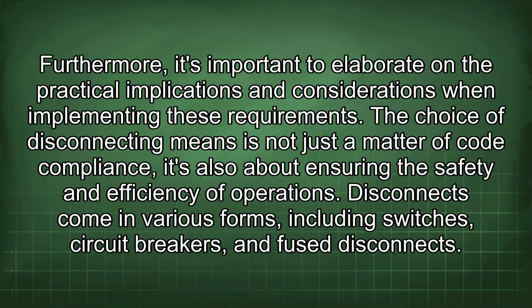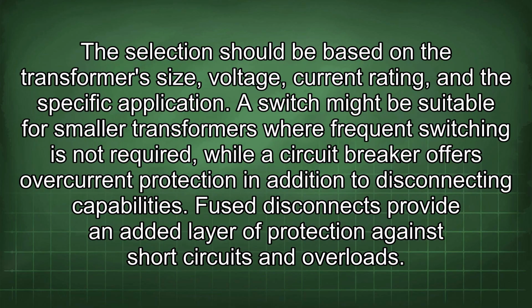efficiency of operation. Disconnects come in various forms, including switches, circuit breakers, and fuse disconnects. The selection should be based on the transformer size, voltage, current rating, and the specific application. A switch might be suitable for smaller transformers where frequent switching is not required, while a circuit breaker offers overcurrent protection in addition to disconnecting capabilities. Fuse disconnects provide an added layer of protection against short circuits and overloads.